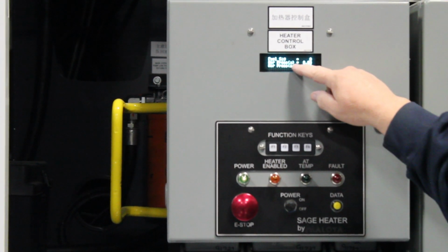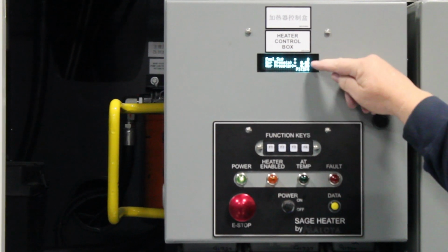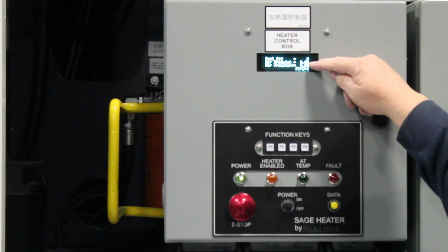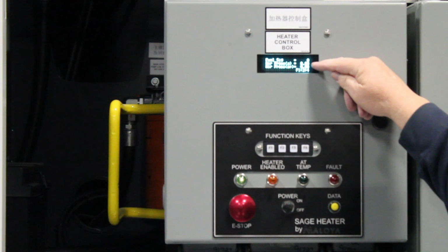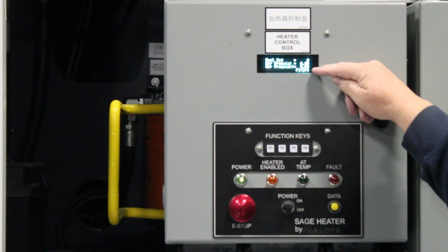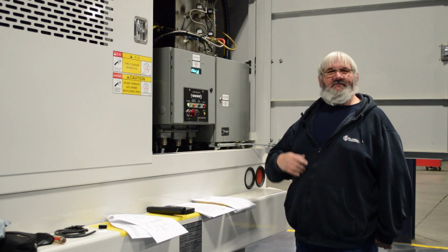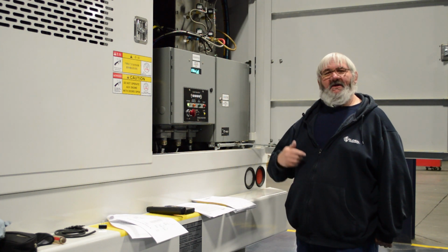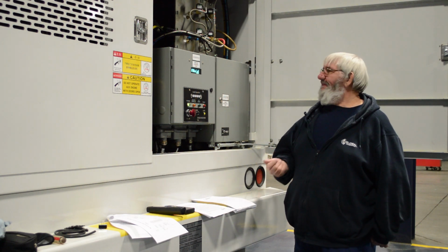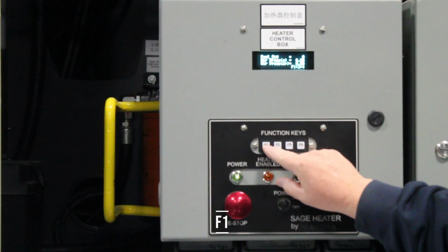So next thing we're going to look at is your air pressure. Your air pressure actual and your air pressure set point. If these two numbers are correct, then you know that your air pressure is correct. But if one of them is high and one of them is low, or vice versa, then that tells you that your problem's on the air side. So you would be troubleshooting your blowers, your air pressure transducer, and your blower control head. Now we'll continue to walk you through the screens.